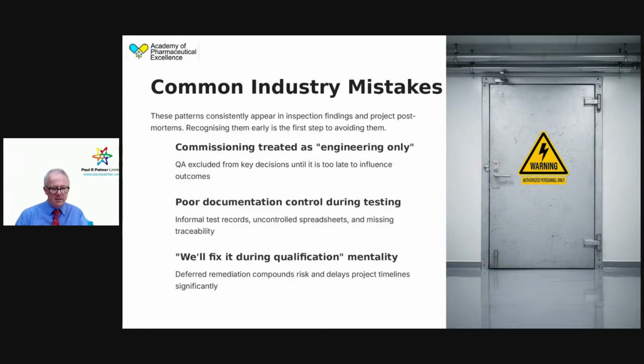But one I have seen many times is: we'll fix it during qualification, we'll fix it when we get to the next stage. The people driving that are usually the manufacturers, because often the contract has an installment of payment on receipt at site. So they want to get to site as soon as possible, even if it puts the equipment in a compromised position and extends timelines, because they haven't got what they need at your site to fix it. But they're always in a rush - push, push, push, everything's fine, let's deliver it. No. You want to make sure you fix the problems as early as possible.